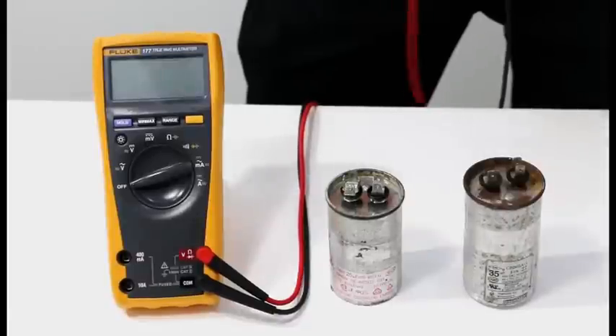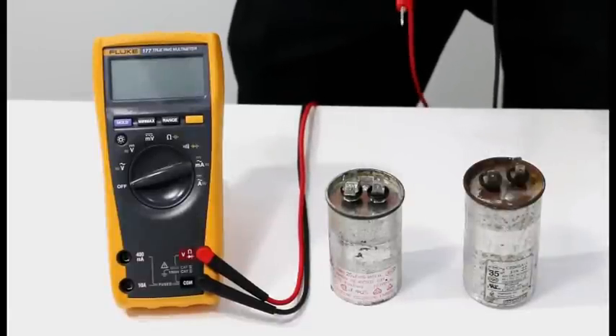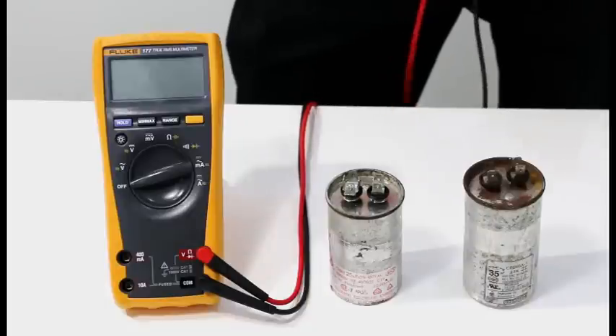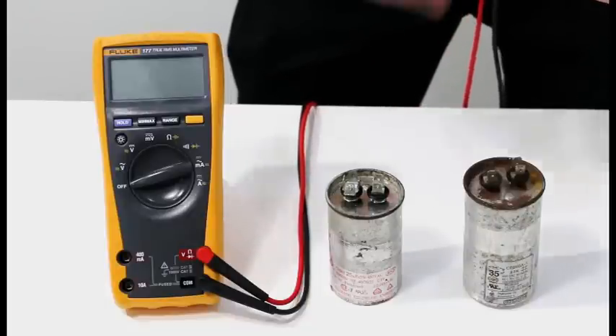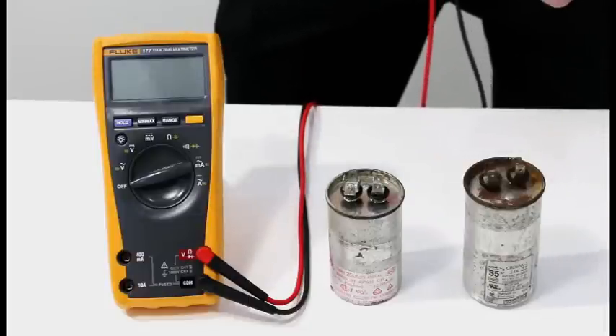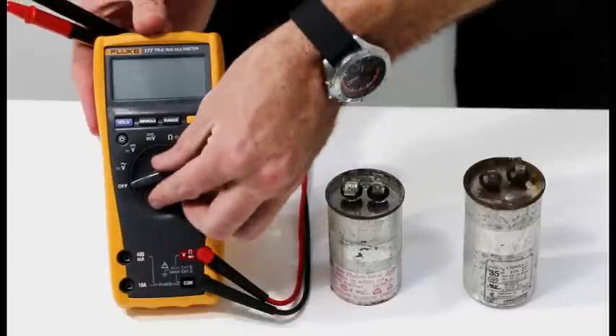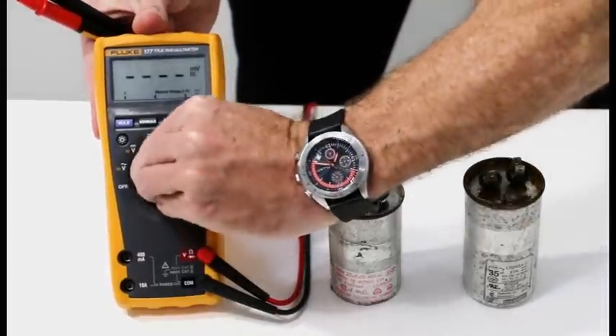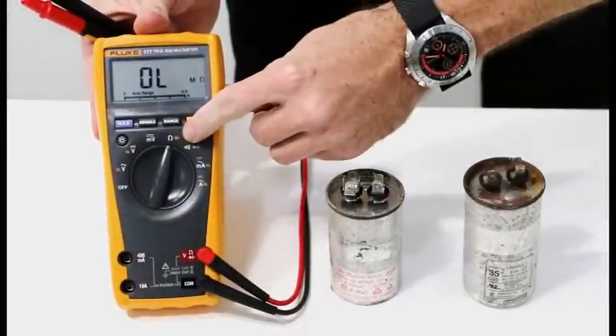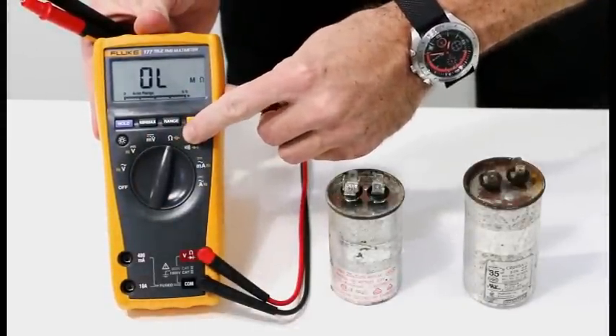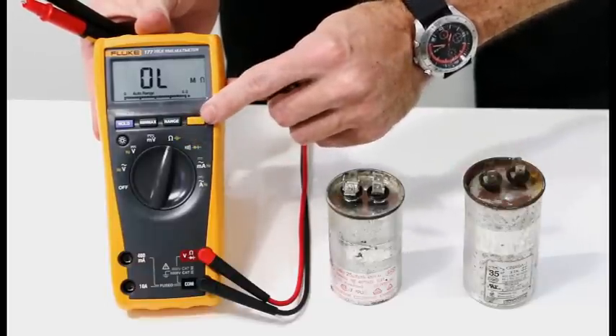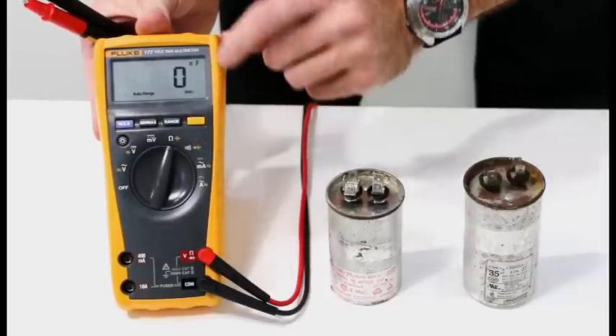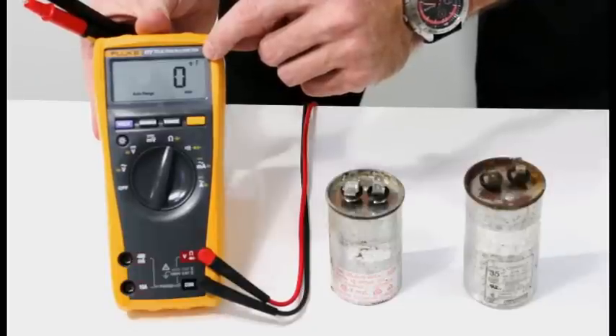We are now going to measure capacitance. I have two capacitors here, one is 25 microfarad and one is 35 microfarad. I know for a fact that one of these has failed. The first thing that we need to do is turn our rotary dial over to our resistance and capacitance function. The capacitance function is highlighted in yellow. I need to press the function key so that it is now moved over to the capacitance function.